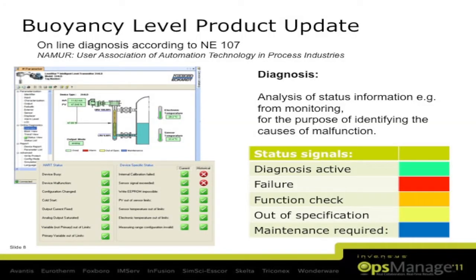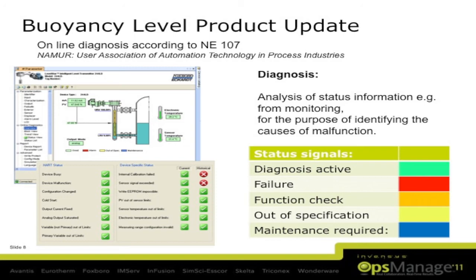So in the overview screen you have all this information in colors. In the detail alarm screen you have all details of the instrument alarms. So you can give priorities to the specific alarms: what is out of range, what is an electronic failure, what is a temperature failure, or what is an application-specific failure for a buoyancy level transmitter. You can select this, and this is available. Also very nice, you have the status from the history. So if this was a failure and it's okay now, only the operator with the access code can delete this. So you always have in view whether the status is coming from a good situation or from a bad situation.